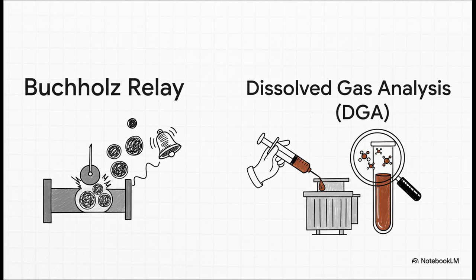And then there's dissolved gas analysis, or DGA. This is literally like a blood test for the transformer. By taking a sample of the oil and analyzing the gases that have dissolved in it, engineers can spot slow-burning problems, we call them incipient faults, way before they turn into a catastrophic failure.